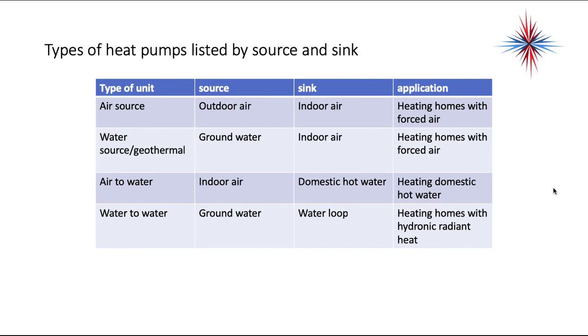So we have different types of heat pumps, and this table lists them by the source and the sink. For an air source heat pump, the source is outdoor air, the sink is indoor air. We use it for heating homes and offices with forced air. Water source or geothermal, the source is groundwater, the sink is indoor air, and again, heating homes or offices with forced air. Air to water, the source is indoor air, the sink is domestic hot water. We use this for domestic hot water heaters. Water to water would be the source being groundwater, the sink is a water loop, and we can use this for heating homes with hydronic radiant heat. Usually water to water is only used in the winter or in heating mode.